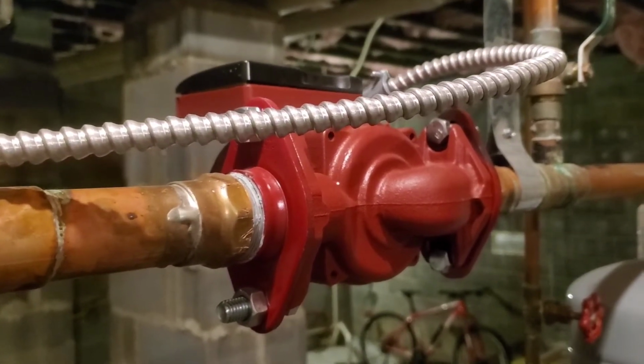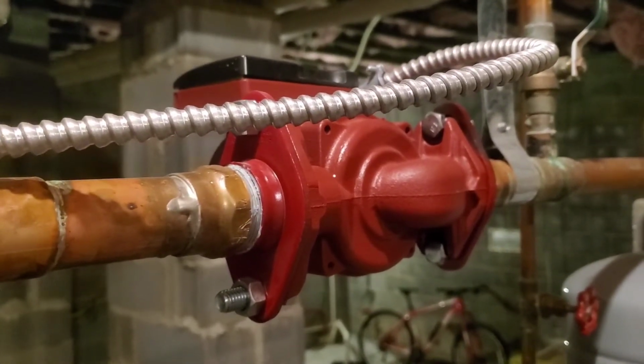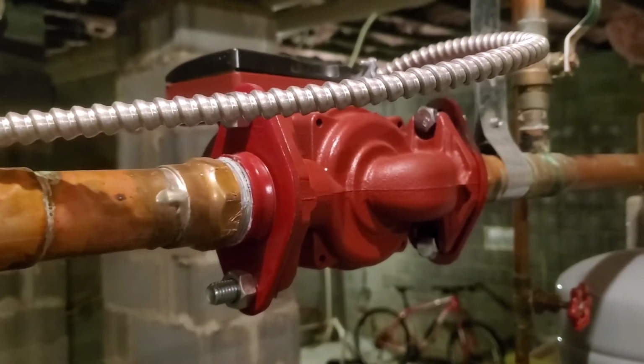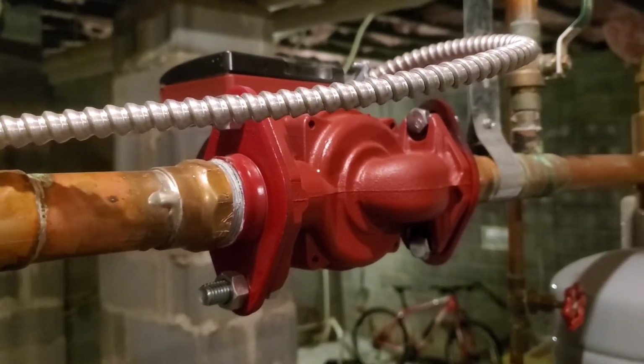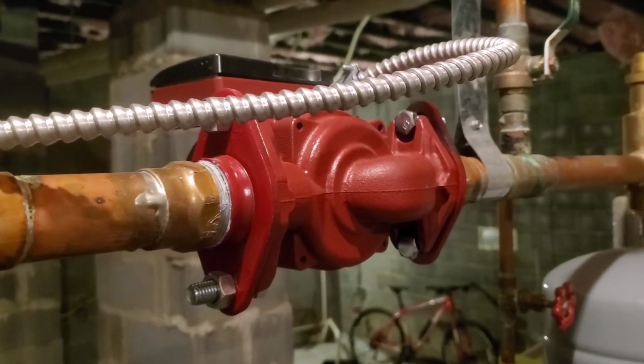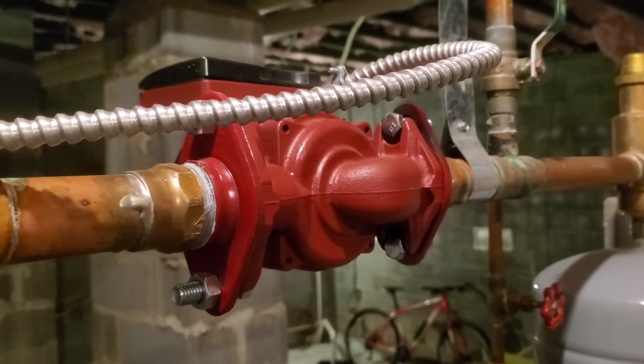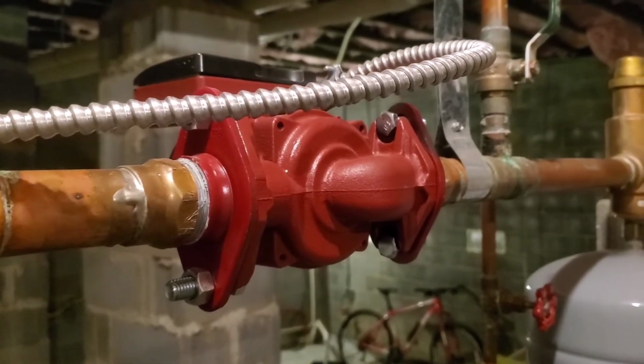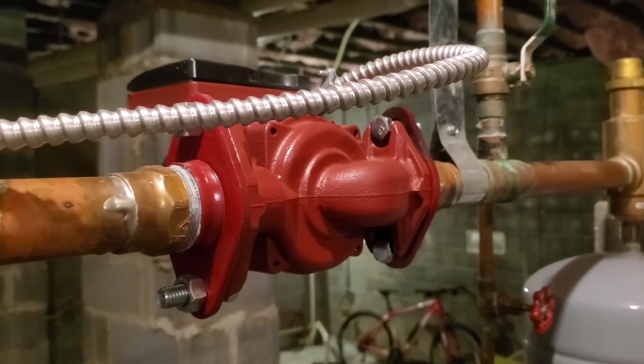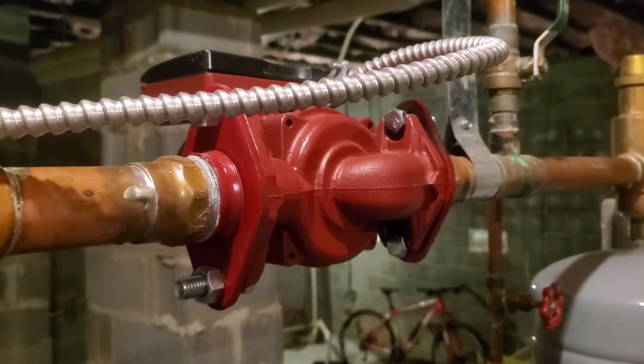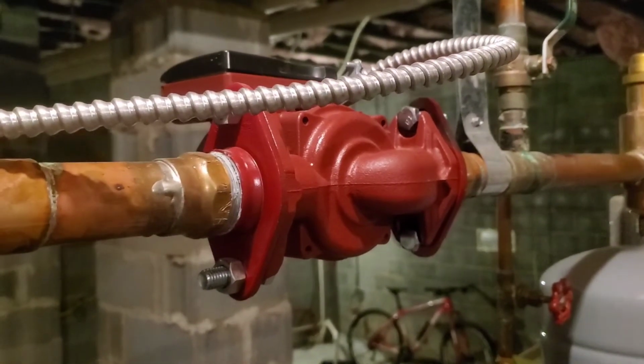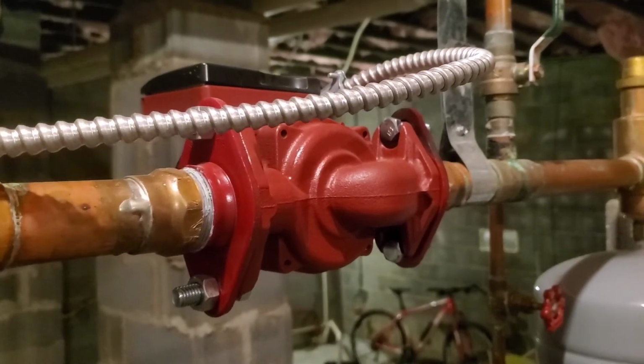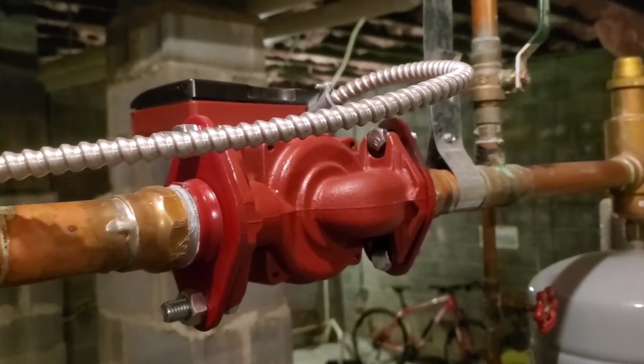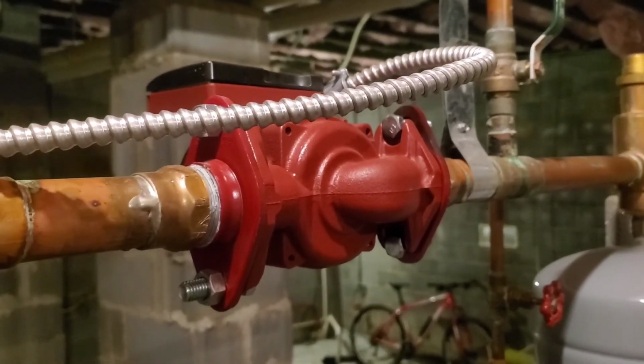Talking to the homeowner, they've lived here 4 years and haven't done anything to it. It's been my experience that you ought to service a boiler every year and bleed the air out of the lines, if nothing else. Of course, clean burners, flame sensors, and if it's oil, do the oil stuff. But I really think that's going to fix this boiler.